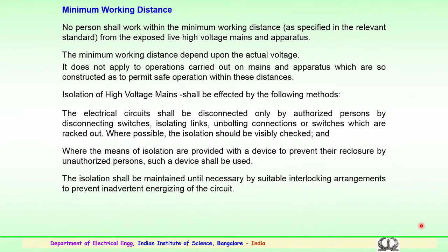No person should work within the minimum working distance. These specifications are mentioned in the relevant standards, and the limits and distances to be followed are described in the international and national standards, from the exposed high voltage mains and also the apparatus or any high voltage equipment. The minimum working distance depends upon the actual voltage level at which the equipment or the transmission is being operated. It does not apply to operations carried out on mains and apparatus which are constructed to permit safe operation within these distances.